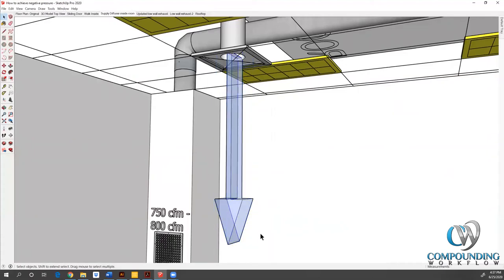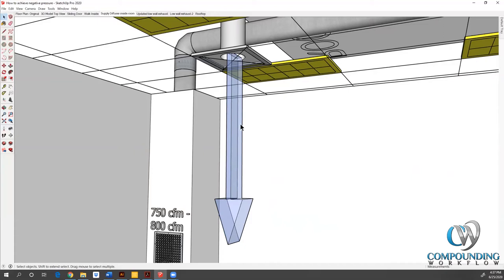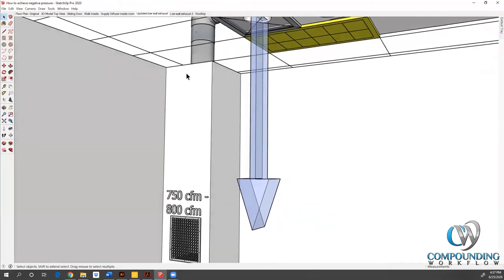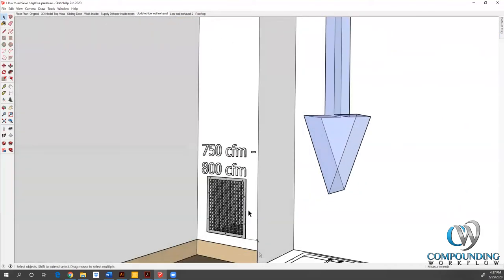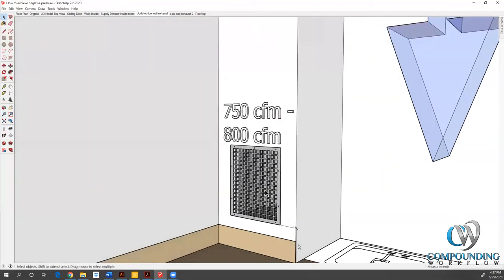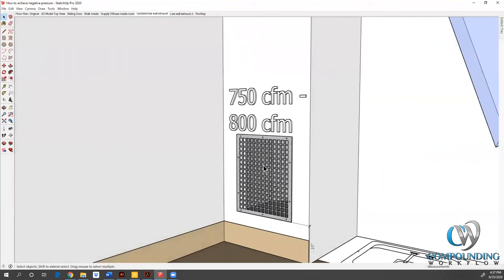Our design goal of a compounding space, we definitely know this in sterile, but I want to carry this thought process over to non-sterile. Our design goal is to move the air from the ceiling down to the floor. Per USP 795, which is also applicable in USP 800 as a non-sterile standard, we must clean that floor every day. If we're dealing with powders in a non-sterile environment and technicians may breach containment or powder exposure, we want to make sure that we push that particulate down to the floor. Maybe it'll statically charge to the floor, maybe it'll impact that floor. But if not, then it'll make it easier to clean or we'll send it out of this low wall exhaust grille.